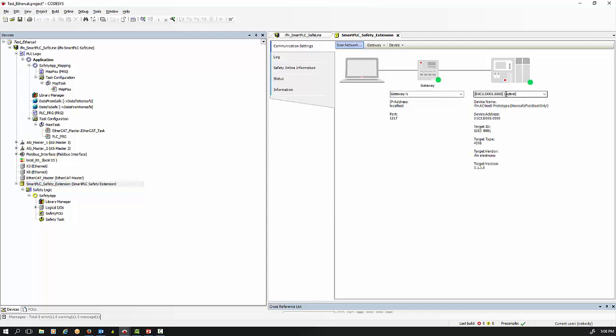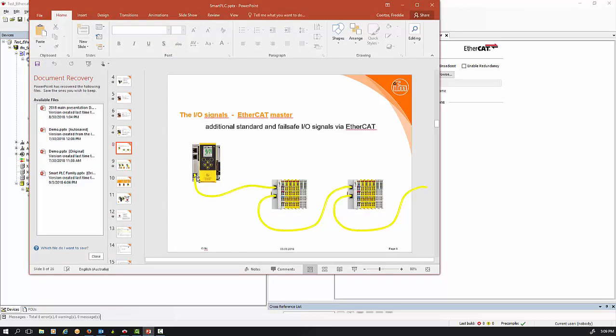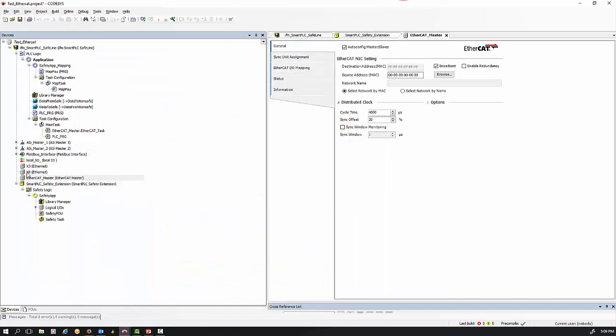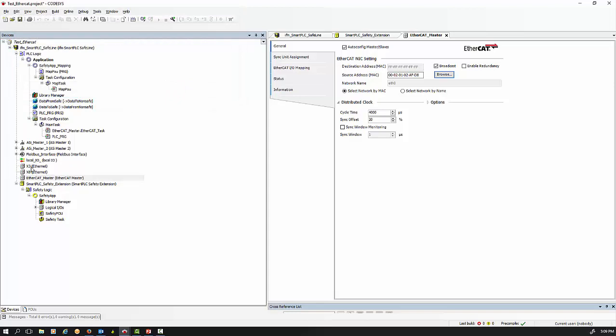After adding that, your device will be online. Go to your EtherCAT master and decide which port it will be under. On a newer device it'll have X3 and X8 — the small extra port added on the left side corner. Ethernet O1 is always port X3, and the second Ethernet port will be port X8. Browse and scan the MAC ID — in this case it comes up with Ethernet O1. Connecting it basically makes port X3 an EtherCAT master.